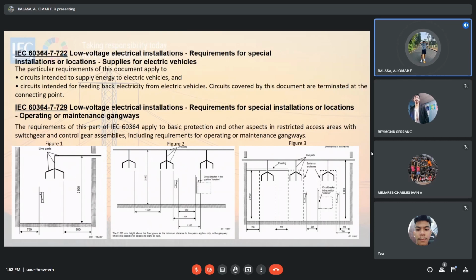Where the protective measure is provided by barriers or enclosures, the following minimum distances apply. Width of the gangway with barriers or enclosures between switch handle and the circuit breakers in isolation position, or switch handles and the wall, 600 mm. Width of the gangway between barriers or enclosures and other barriers or enclosures, or the wall, 500 mm. Height of paneling above the floor, 2,000 mm. The height of live parts above the floor, 2,500 mm. Where additional workspace is needed, for example for special switchgear and control assemblies, larger dimensions may be required.